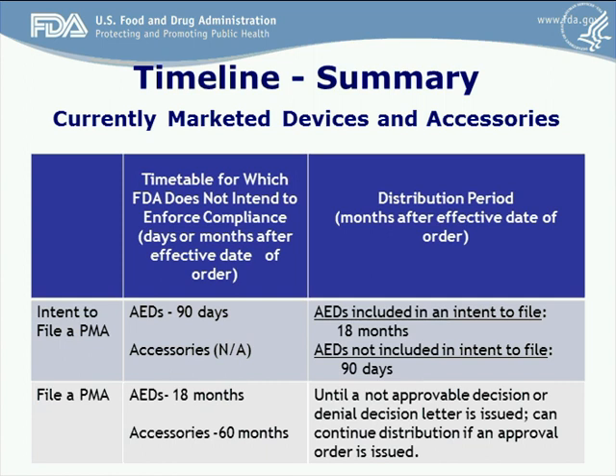The timeline for filing a PMA for AED devices that are currently on the market is within 18 months, and for accessories, it's within 60 months. You may continue to distribute those devices that are included in a PMA until a not approvable decision or denial decision letter is issued, and of course, you can continue distribution if an approval order is issued.